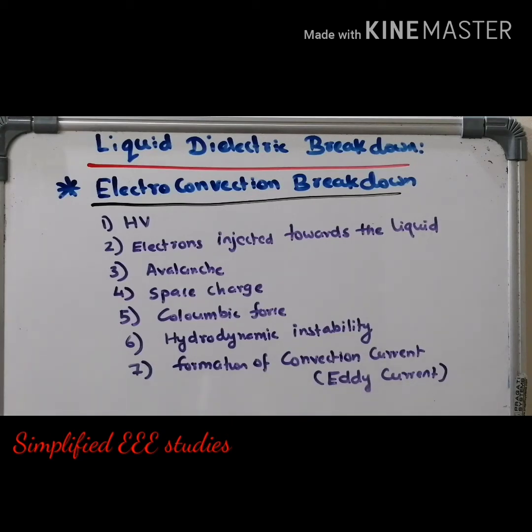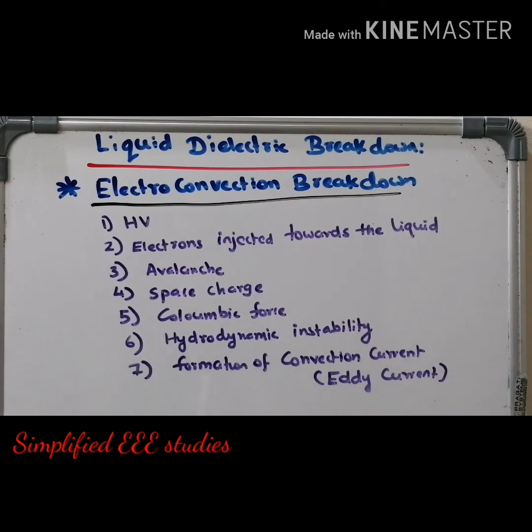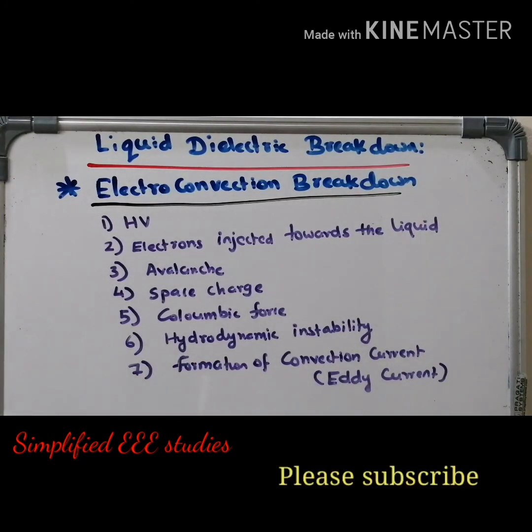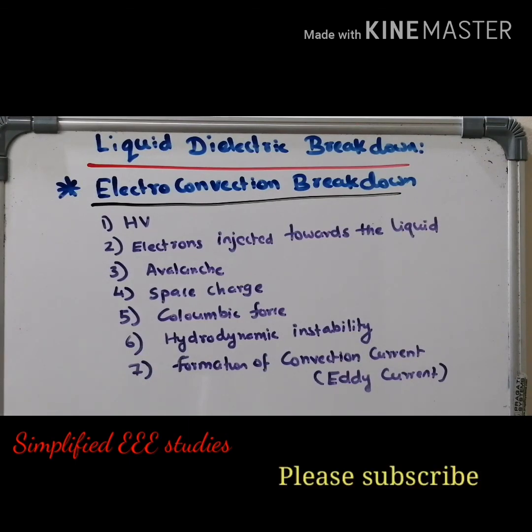Let me conclude. This theory concerns liquid dielectric breakdown and is known as electroconvection breakdown. When you apply high voltage, electrons are injected towards the liquid dielectric media. As a result, an avalanche forms, which leads to space charge formation. Because of the space charge, Coulombic force is generated, resulting in hydrodynamic instability. Once hydrodynamic instability occurs, the entire phase of the liquid is changed, causing the formation of a convection current — also known as eddy current — inside the liquid dielectric media. As a result of this current, the property of the liquid dielectric media is changed, and we conclude that dielectric breakdown of liquid dielectric media has occurred.